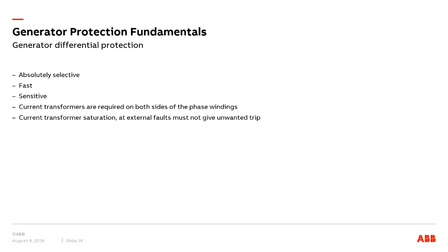So what is the feature of a generator differential protection? Like all other differential current protection schemes, generator differential protection is also absolutely selective. This means that only faults within the protection zone are detected. The protection zone means the zone between the current transformers. I have a scheme coming up in the next slide. So there are two sets of current transformers required to achieve the differential protection. So the fault within the zone is to be acted upon by this differential protection. Faults in the connected network are not detected. The generator differential protection can thus not be used as a backup protection for external faults. So it's a unit protection.